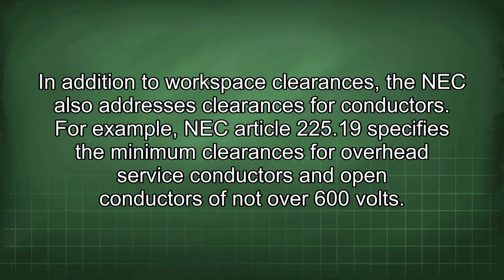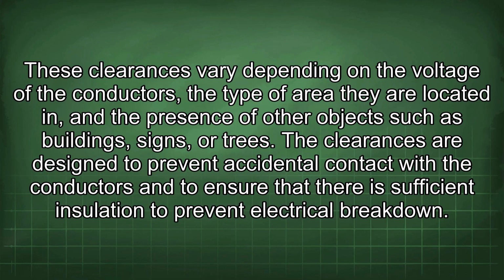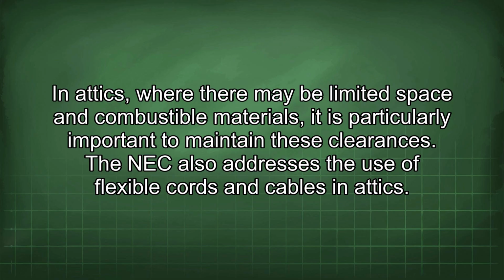In addition to workspace clearances, the NEC also addresses clearances for conductors. For example, NEC Article 225.19 specifies the minimum clearances for overhead service conductors and open conductors of not over 600 volts. These clearances vary depending on the voltage of the conductors, the type of area they are located in, and the presence of other objects such as buildings, signs, or trees. The clearances are designed to prevent accidental contact with the conductors and to ensure that there is sufficient insulation to prevent electrical breakdown. In attics, where there may be limited space and combustible materials, it is particularly important to maintain these clearances.